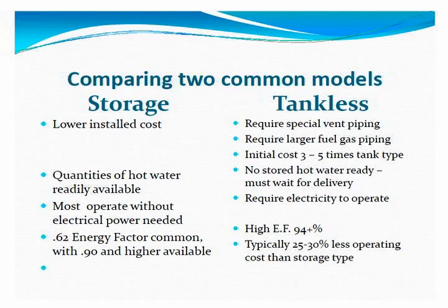So now let's take a look at comparing the two most common models we run into today. We have a storage type water heater and the tankless units, as we've mentioned. A storage unit has a lower installed cost than a tankless model. You have a quantity of hot water that's readily available. Turn on the tap and you have hot water. And most of these operate without the need for electrical power, that is if they are propane or natural gas powered. The problem is efficiency. About a 0.62 energy factor is most common, but there are a few models, for a very high cost, that can have a 90% or greater efficiency factor.